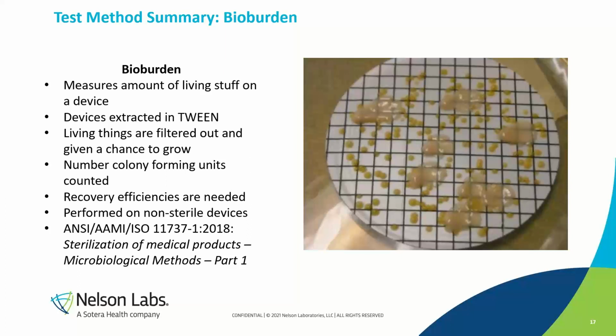For the purposes of a cleaning validation, bioburden is performed on non-sterile devices. We don't want these sterilized. This is not intended to substitute as a sterilization validation. It's really just intended to ensure that coming out of your final clean, your devices do not have such an outrageous organism count that it would later impede a sterilization process. So we do want these non-sterile.